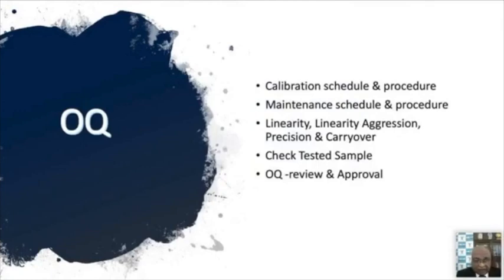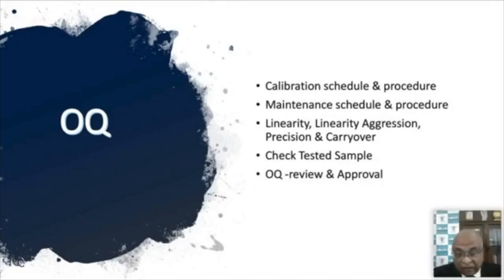Then in operation qualification, calibration schedule and procedure. This calibration, if required, shall be with the help of a calibrator, and the calibrator shall have metrological traceability. Then proper maintenance schedule, and what is the procedure of that maintenance. Then define in your laboratory linearity, this regression analysis, precision, and carryover for different analytes if required. Then check tested sample after running control. Then all these documents are reviewed and approved by authorized signatory, and again signed by the laboratory person as well as the company person.